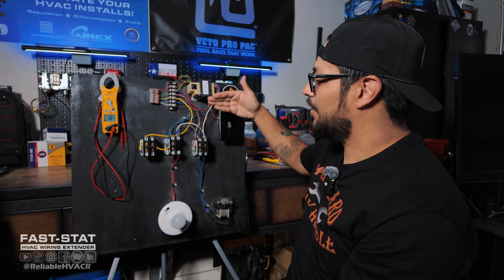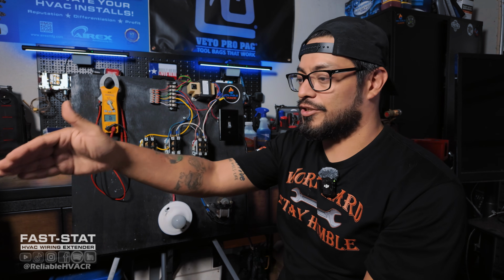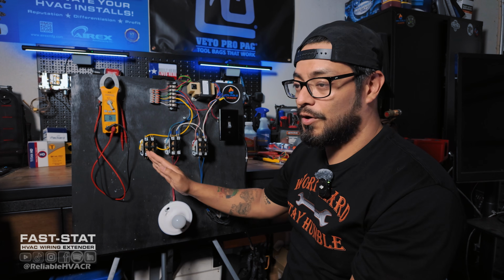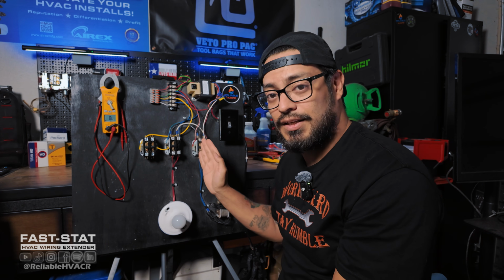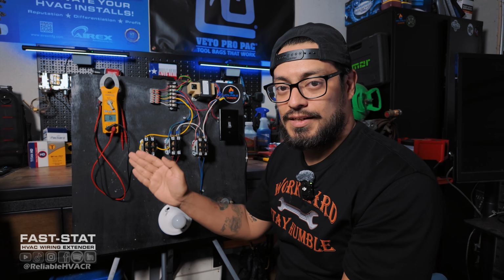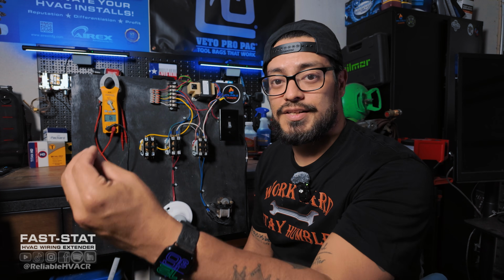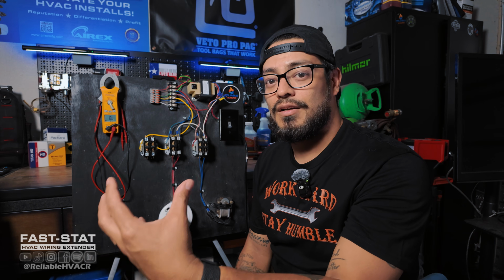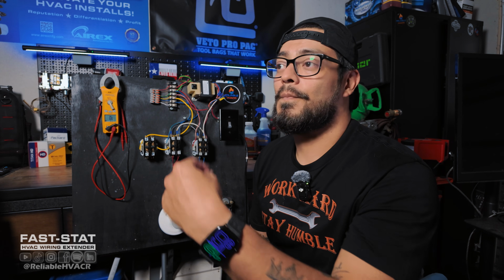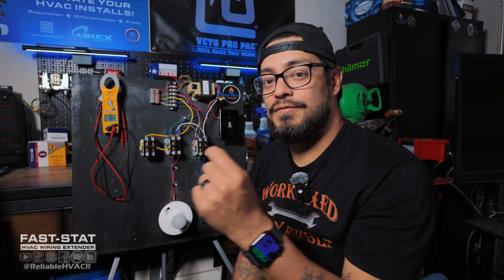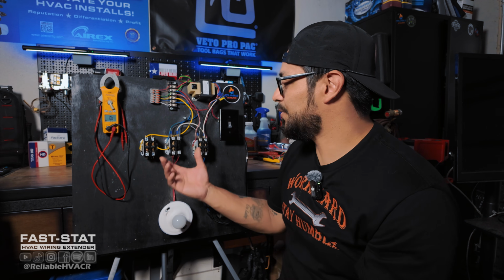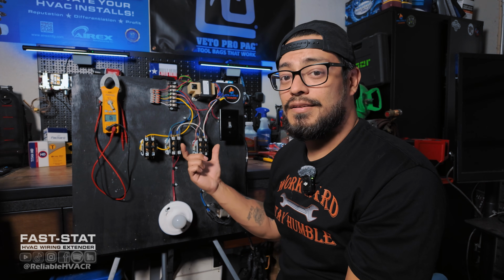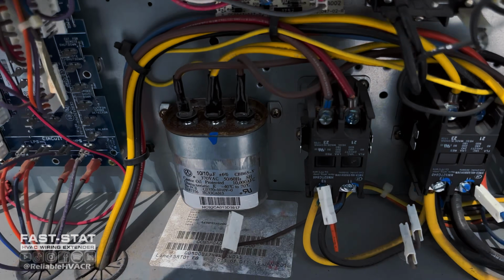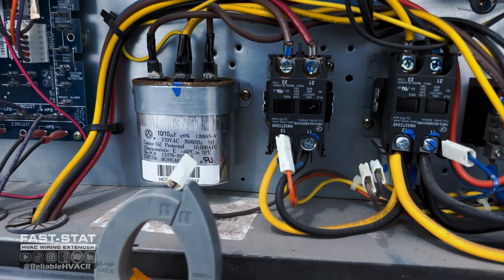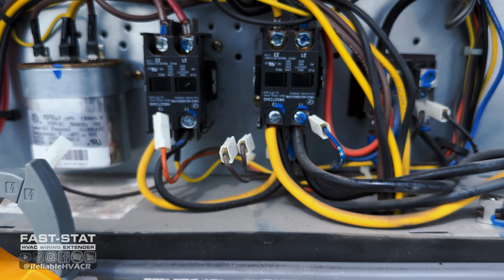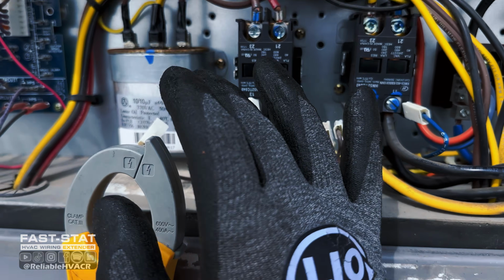If you figure out that it is shorting out on a blower motor or cooling or heating, you can also go to that contactor. Like if it's a residential, you can go outside. If it only shorts out, blows a fuse on cooling, you can go outside and check that contactor. If you guys are working on RTUs, typically they're going to have a few in line. Sometimes a blower has its own contactor. Sometimes it's in line with another one. Sometimes it goes through a relay. But you can start with the contactors themselves.